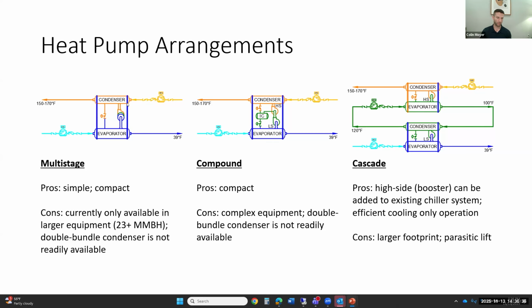So if you want to purpose this as a chiller only, you end up with pretty inefficient cooling because you have to make hot water and then use heat exchangers. The compound machine we were looking at for a number of years for UC Davis consists of two separate compressors that are essentially in series, but their refrigerant flow is balanced out by an intercooler. So this is like the traditional York CYK.